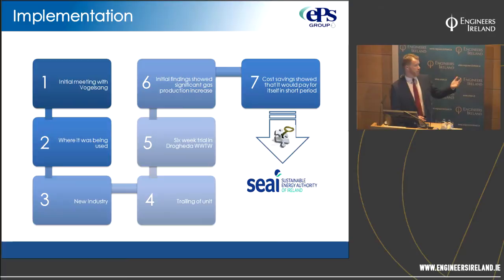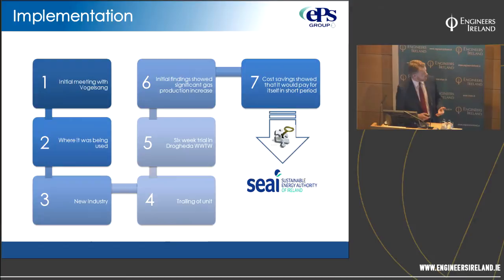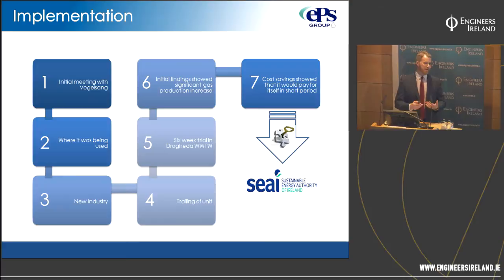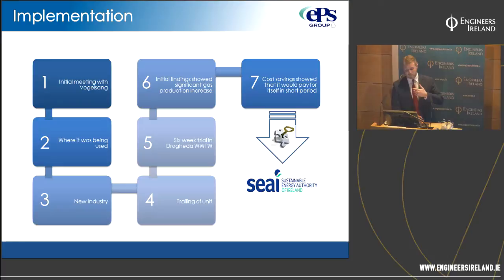We met with Vogelsang about moving BioCrack into municipal wastewater — an area where they had no existing references but were interested in developing. They conducted in-house trials comparing municipal wastewater to the agricultural maize and dung they had been digesting, and found very positive results. We then progressed together with a six-week trial at a treatment plant in Drogheda, placing the unit on the recirculation line of one of the digesters. Drogheda was chosen partly for its very low sludge retention time.